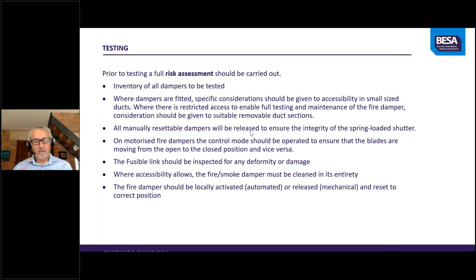I'm just closing my little slide there, which has come out some of the information. And on motorized fire dampers, control mode should operate to ensure that blades are moving from the open and closed position and vice versa. The fusible link should be inspected for any deformity or damage, and where accessibility allows, the fire/smoke damper should be cleaned in its entirety. The fire damper should be locally activated or released mechanically and reset again in its correct position. Next slide, please.